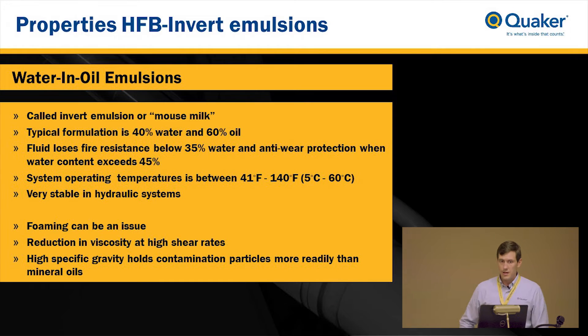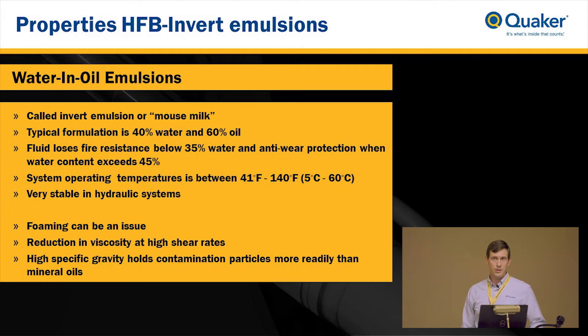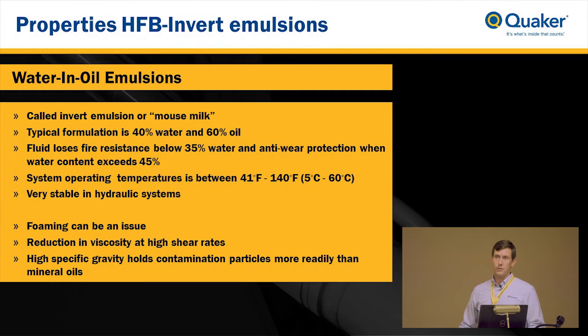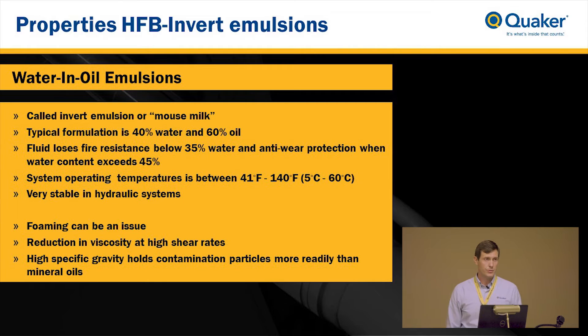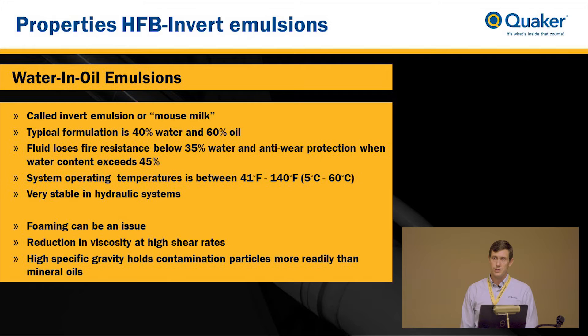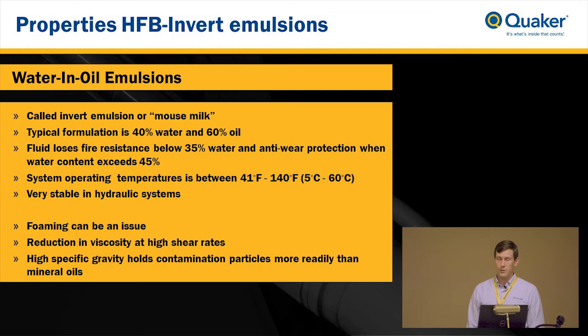The second category is HFB, the invert emulsion — about 40 percent water into 60 percent oil, the exact opposite of a regular emulsion, with water inside the oil mixture. This is probably the lowest used fire resistant hydraulic fluid. In the old days it was called mouse milk, and people used it underground in place of a mineral oil based hydraulic fluid.